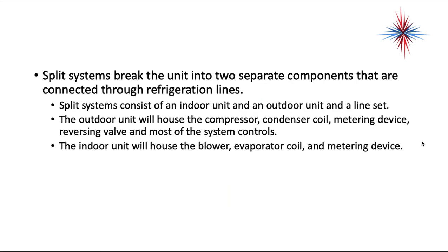Now, split systems are different than the package units because split systems break the unit into two separate components. They're connected through refrigeration lines. Split systems consist of an indoor unit, an outdoor unit, and a line set. The outdoor unit will house the compressor, condenser coil, metering device, reversing valve, and most of the system controls. The indoor unit will house the blower, the evaporator coil, and the metering device. Notice there are two metering devices in split system heat pumps.